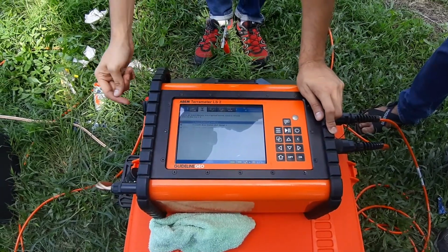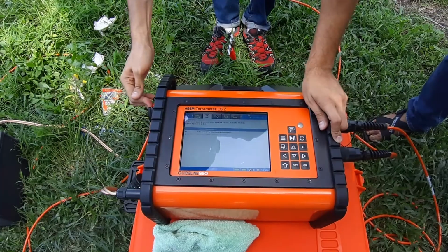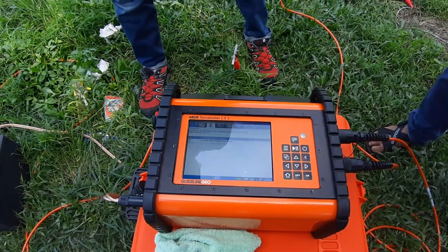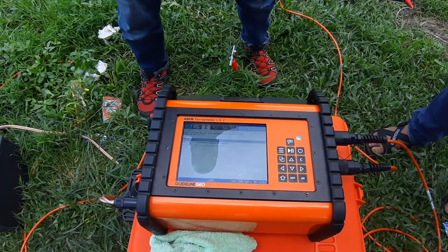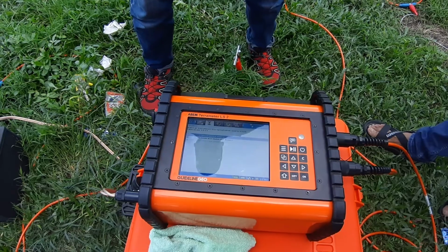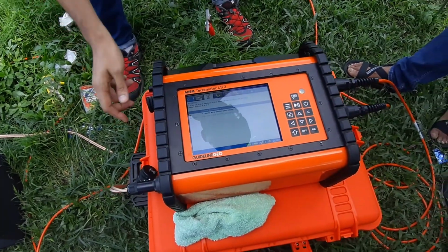Safety switch, stop here. Twist. When you press this safety button, it will stop measuring everything. Let's say during rainy days, suddenly you want to lift up the equipment. Just press this button and it will shut down everything. No current leaks from the instrument. So this is safety, and then start measuring.